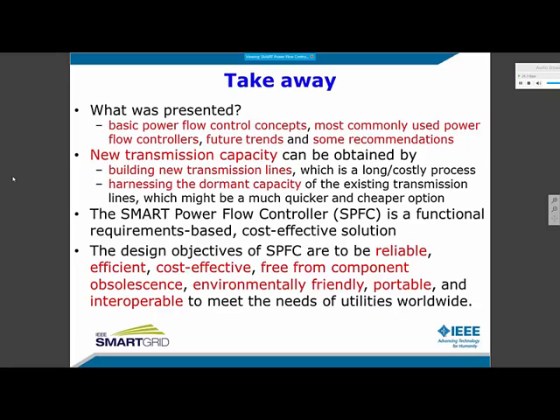So what do we take away from this presentation? The takeaway is that I presented the basic power flow control concepts, most commonly used power flow controllers, future trends, and some recommendations. Now, new transmission capacity can be obtained by either building a new transmission line, which is a long and costly process, or harnessing the dormant capacity of the existing transmission lines, which might be a quicker and cheaper option. The smart power flow controller is a functional requirement-based cost-effective solution.